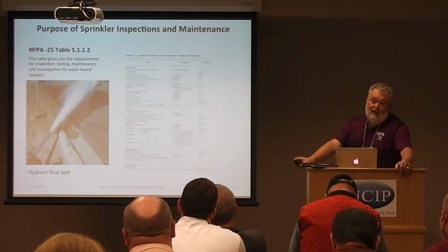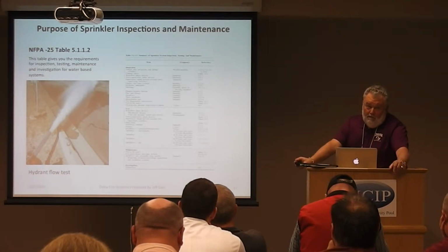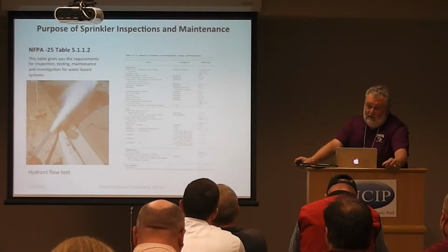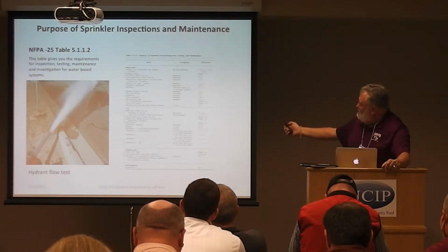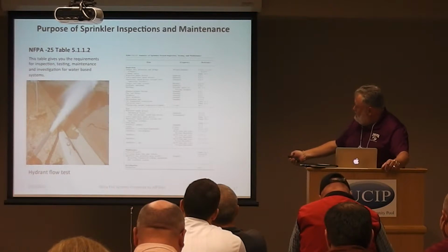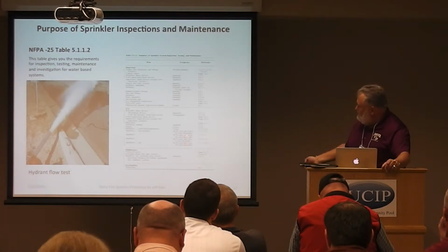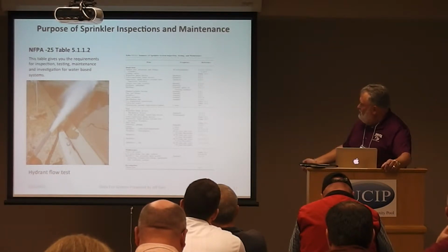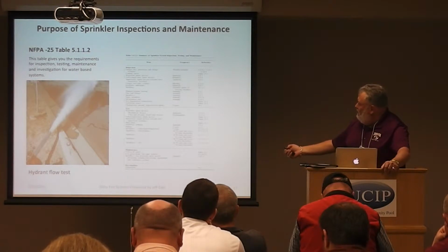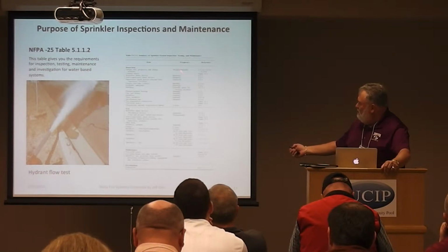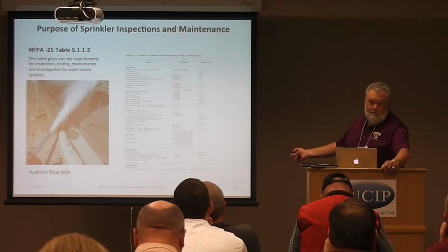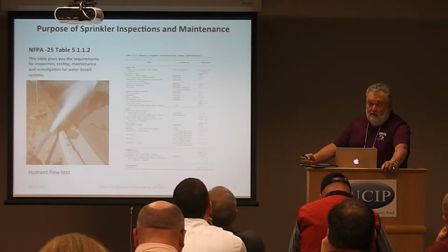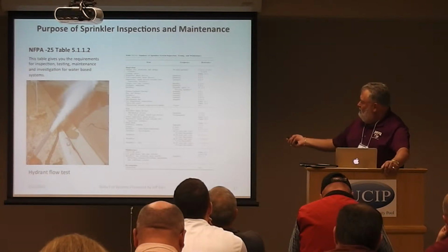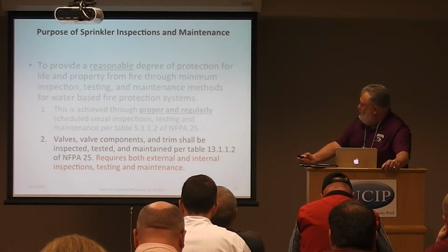Okay, this is that table, and as part of this, I've sent over, and I hope you'll be able to get copies of all these inspection forms. They're standard right out of NFPA 25, and they break this down pretty clear into 3 sections. This is what's required for inspections, here's the testing requirements, and here's the maintenance requirements of all the water-based systems. And you can see, for instance, here on gauges, they should be looked at on a pre-action and deluge system weekly or monthly. But those same gauges on a wet system only have to be looked at monthly. So, I would recommend that you follow these, and they would help you immensely on these here.